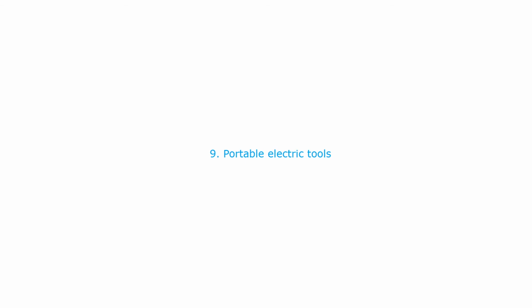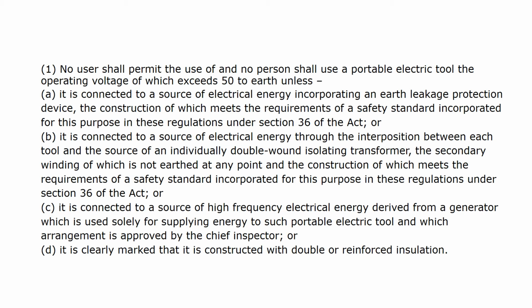Portable electric tools. No user shall permit the use of and no person shall use a portable electric tool the operating voltage of which exceeds 50 to earth unless A. it is connected to a source of electrical energy incorporating an earth leakage protection device, the construction of which meets the requirements of a safety standard incorporated for this purpose in these regulations under Section 36 of the Act, or B.